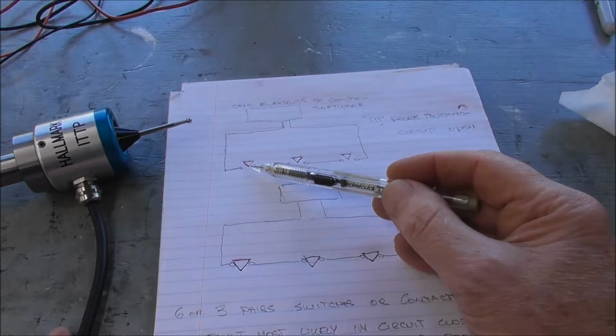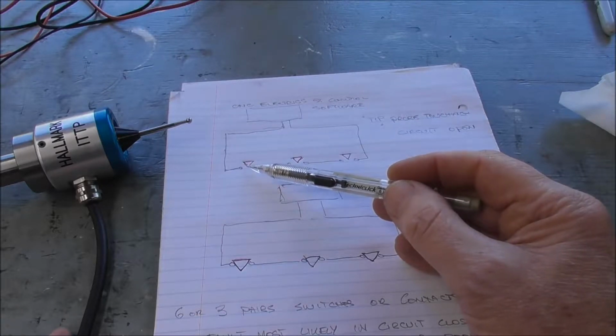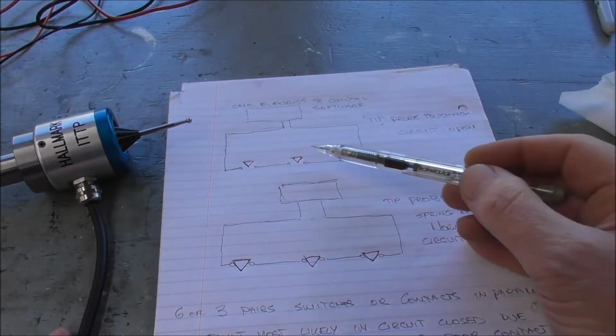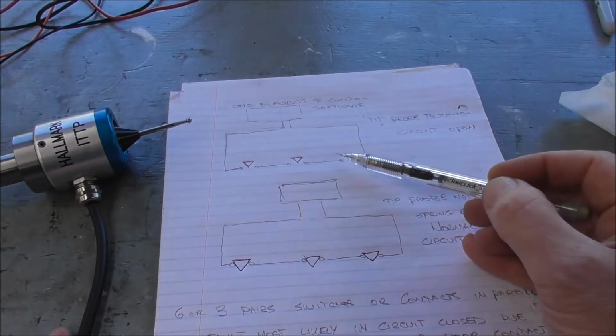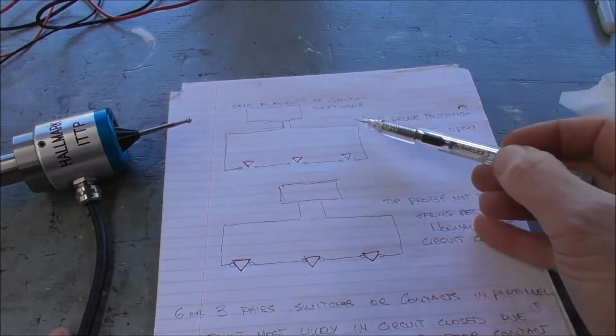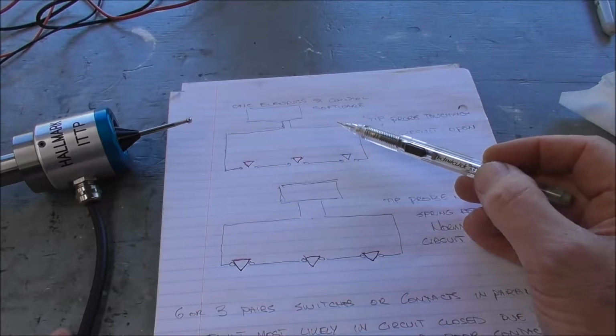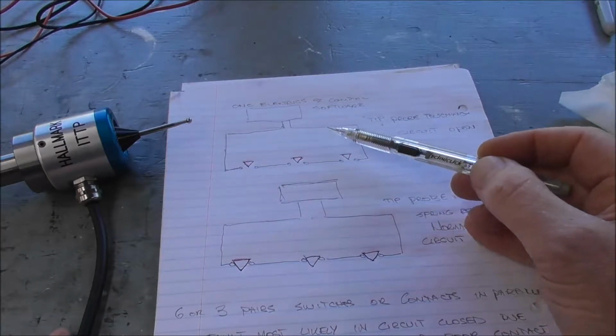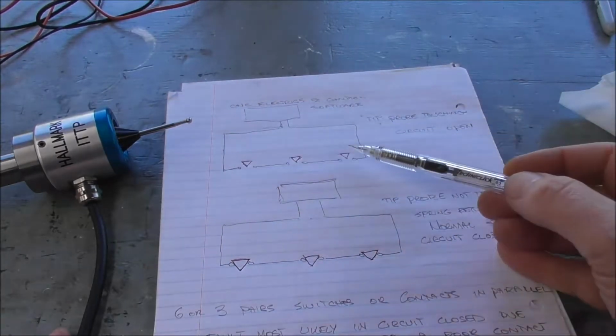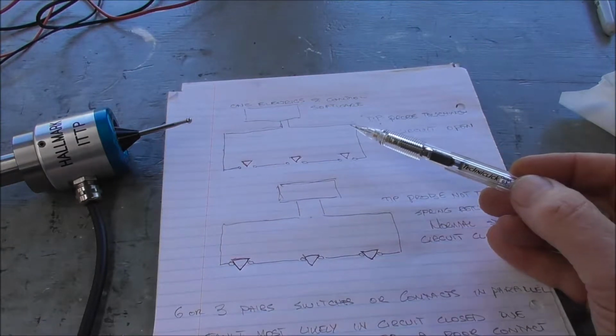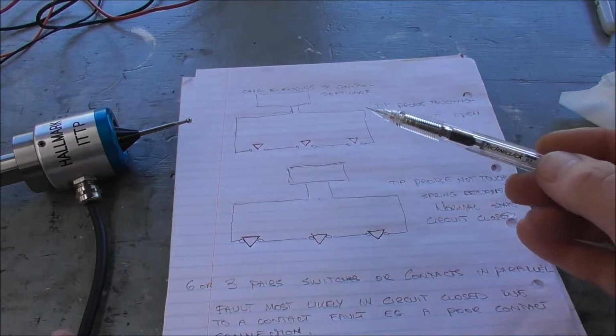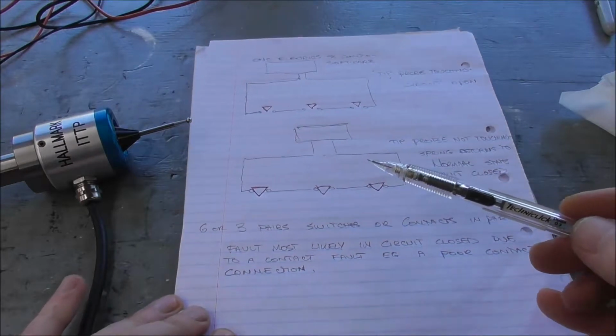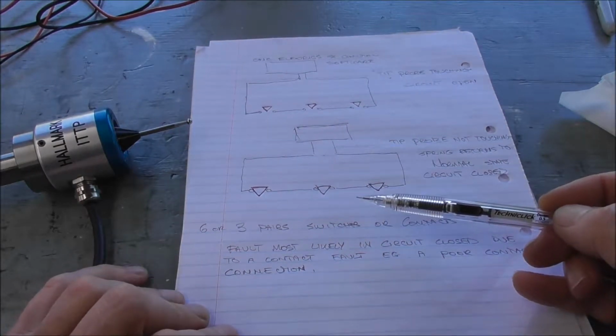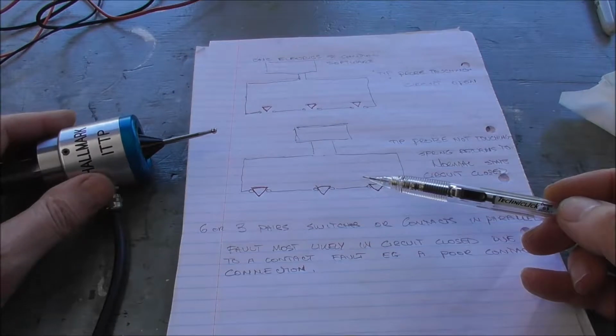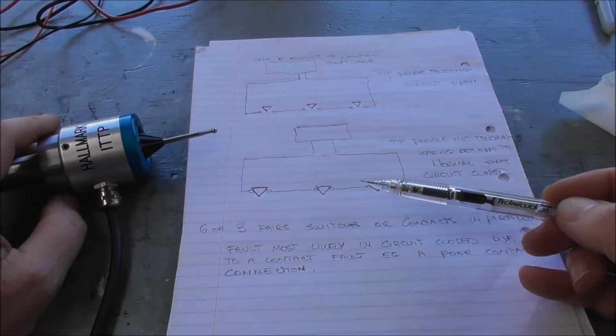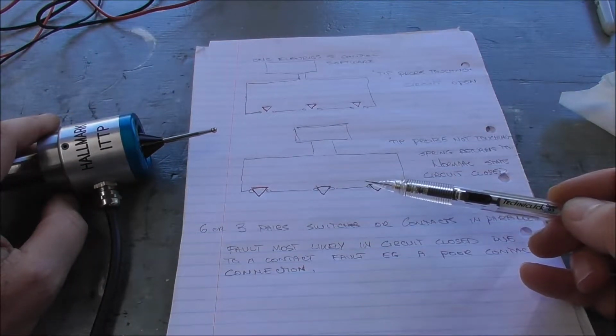Now it may only be half of one of those switches, one of those 6 contacts broken, but here I'm just showing all 3 open. So now the circuit is open and the control software is tripped and showing an open circuit. Okay, so the fault is most likely to be, and just as a note, it's this probe, the Hallmark probe, has proven to be very reliable in in-house testing and all beta testing so far.